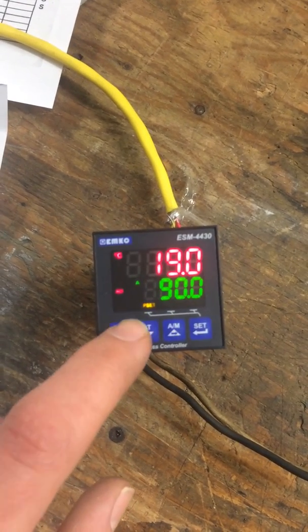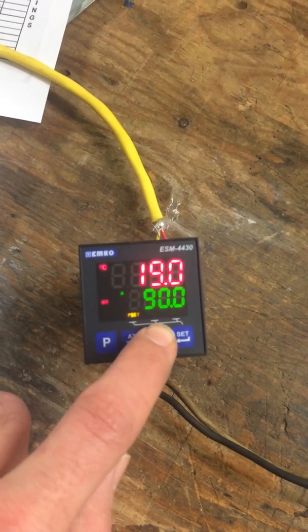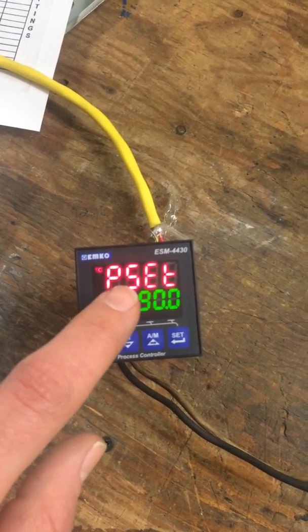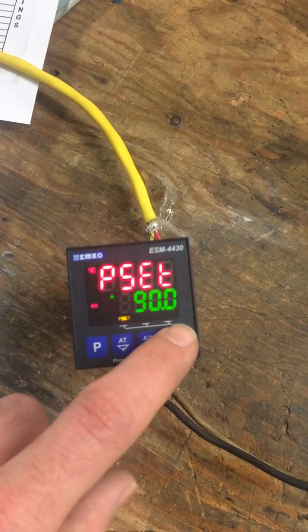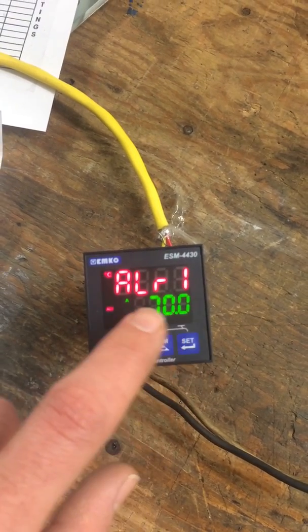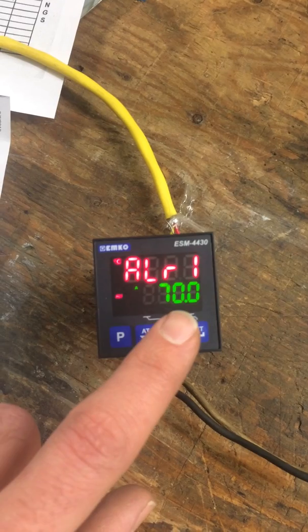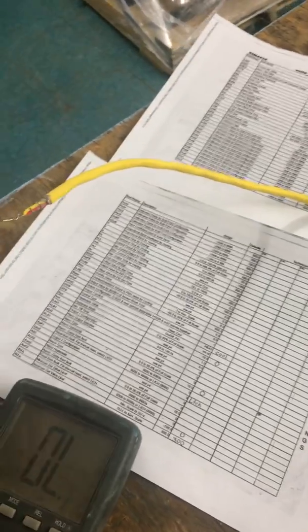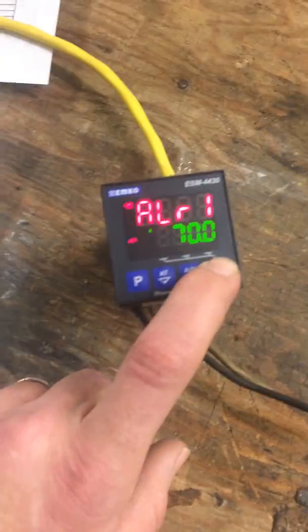Push P. Now we have a current reading — ambient, I'm reading 90. I'm not adjusting anything with these buttons because this is just the current process screen. Push the set button — this is your preset. In reality, this doesn't have any functionality over this control because we're not using this as a heater or cooler. Push the set function again — Alarm 1. It's set up for 70°C. Typically we send these out at 300°C, but I would like to leave it at 70. I'll attach the wire with the sensor on the end — it is a Type-K thermocouple wire. In this instance, I just wrapped it to give me an alarm output.